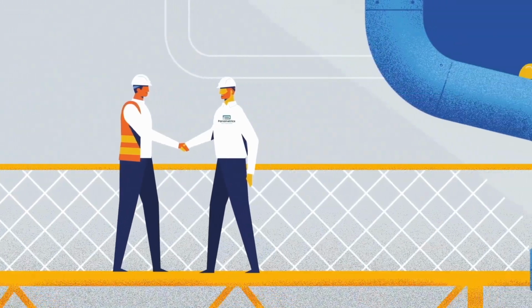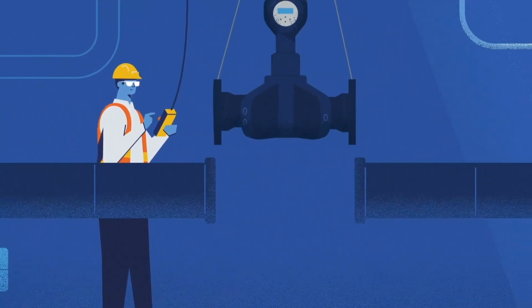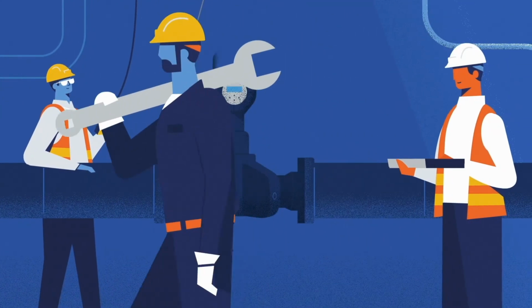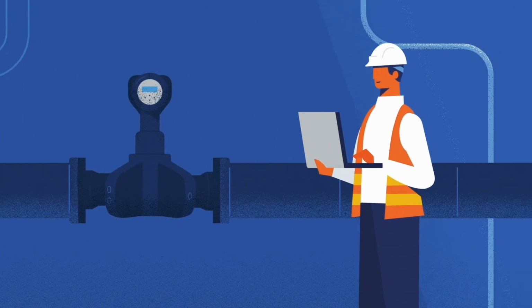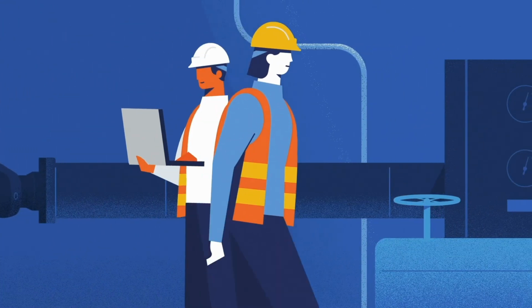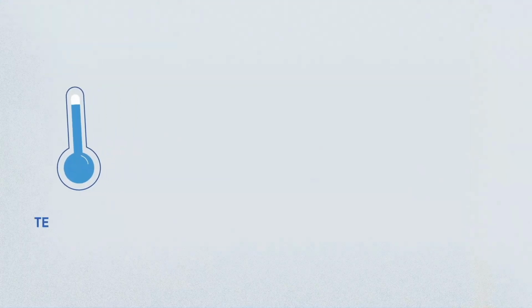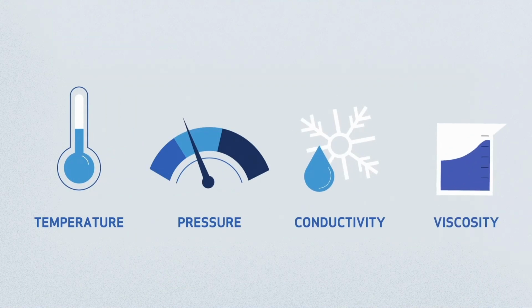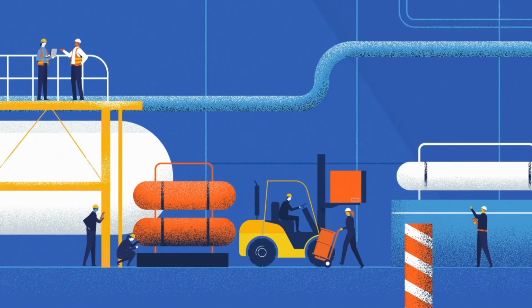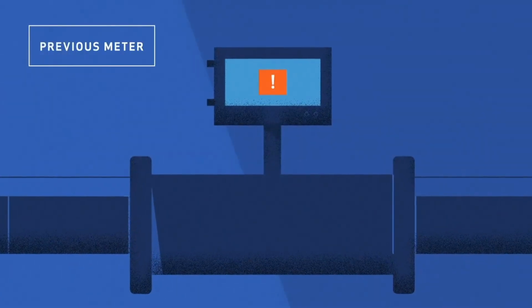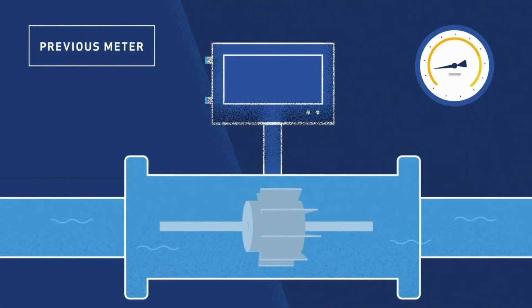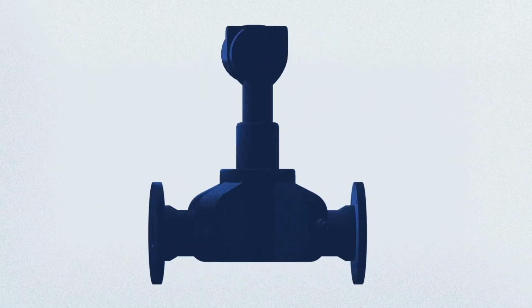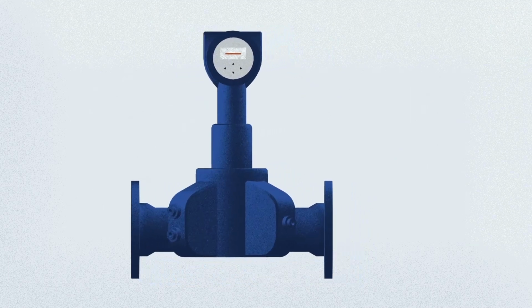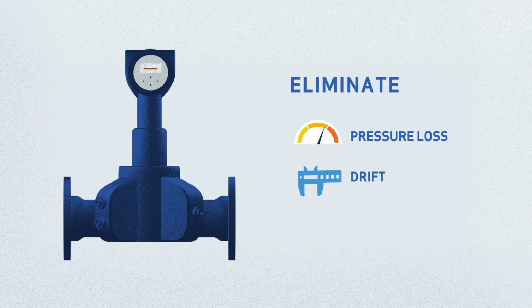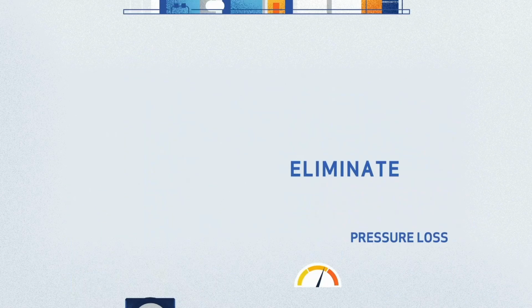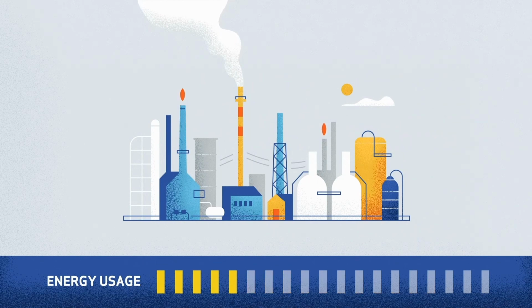That's when they got together with Baker Hughes and were recommended Panaflow ultrasonic liquid flow meters. The engineers knew these ultrasonic flow meters would save them time and money in the long run on things like maintenance and calibration. They also knew that ultrasonic flow meters work independently of temperature, pressure, conductivity, and viscosity, which was especially helpful for these guys. The previous flow meter couldn't handle the viscous product, causing a pressure loss that reduced pump efficiency. With no moving parts, no restriction in the pipe, and a full-bore flow cell design, the Panaflow meters eliminate pressure loss, drift, and any degradation of flow. They also reduce the plant's energy usage by improving pump efficiency.